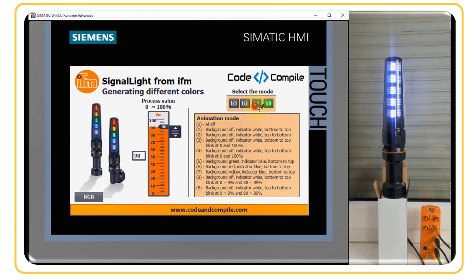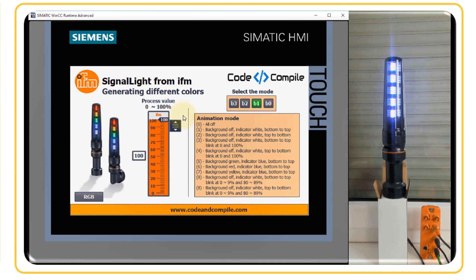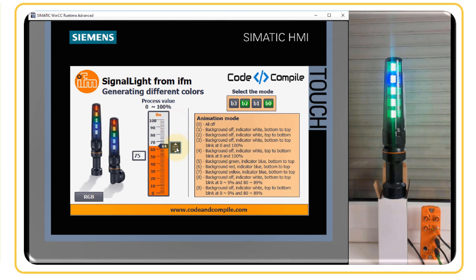Mode two reverses the animation — it animates from top to bottom. At 10 percent, the top segment is on. As the process value increases, the light animates from top to bottom. Mode five: background green, indicator blue, bottom to top (binary 101). The indicator is blue and background is green; as the process value decreases, the blue indicator moves down proportionally.